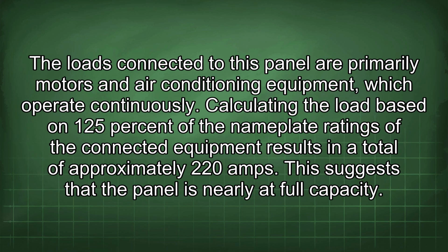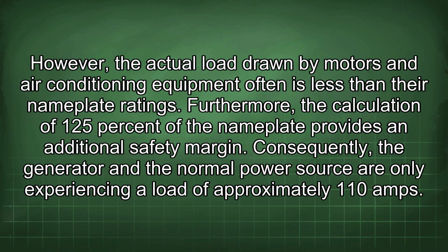The loads connected to this panel are primarily motors and air conditioning equipment, which operate continuously. Calculating the load based on 125% of the nameplate ratings of the connected equipment results in a total of approximately 220 amps. This suggests that the panel is nearly at full capacity. However, the actual load drawn by motors and air conditioning equipment often is less than their nameplate ratings. Furthermore, the calculation of 125% of the nameplate provides an additional safety margin. Consequently, the generator and the normal power source are only experiencing a load of approximately 110 amps.